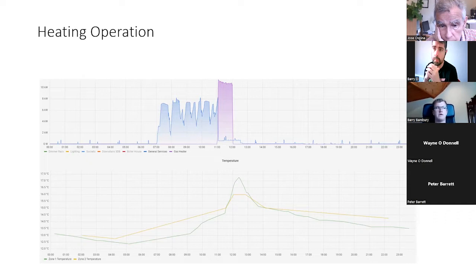Again, bear in mind that if we were to heat up this entire building, if we were to leave the air source heat pump on for 24 hours, which is what you normally do, it's our expectation that on the colder days in winter it would still struggle to reach that 17-degree set point, just because of how poor the fabric is and how great the heat loss through the building would be at nighttime. And it would still cost the church about 50 euros per day. In a lot of instances, we expect you might still need to supplement with gas on colder days. So leaving it run for 24 hours, just because of the nature of the building, we don't believe is a suitable solution.